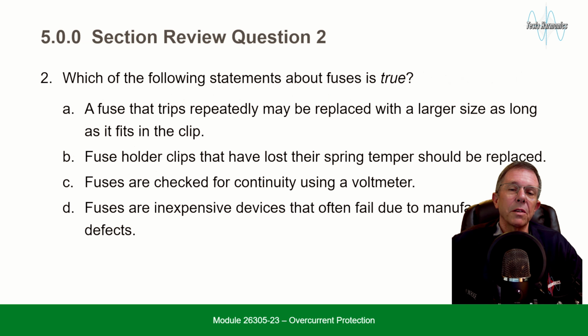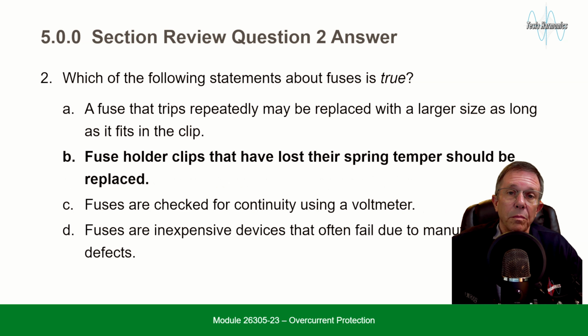Which of the following statements about fuses is true? A fuse that trips repeatedly may be replaced with a larger size as long as it fits in the clip. Fuse holder clips that have lost their spring temper should be replaced. Fuses are checked for continuity using a voltmeter. Or D, fuses are inexpensive devices that often fail due to manufacturing defects. That's going to be B. Fuse holder clips that have lost their spring temper should be replaced.